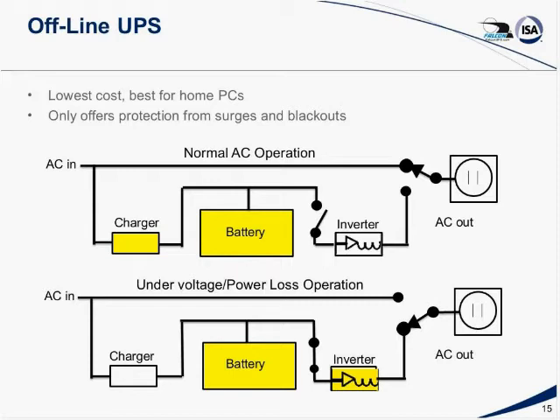Now, when you have a power outage, look at the lower diagram. Then we switch over to the battery-operated inverter. Of course, the charger is not charging now because the AC is not there. But the battery is operating the inverter, and you're getting AC out. And these run all the way from square wave to sine wave. Again, it only protects against utility blackouts and limited voltage and transient protections. And you get about as much protection with a surge strip.